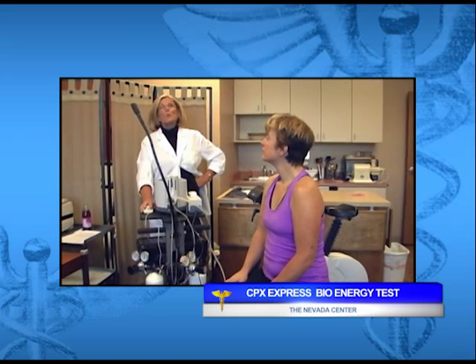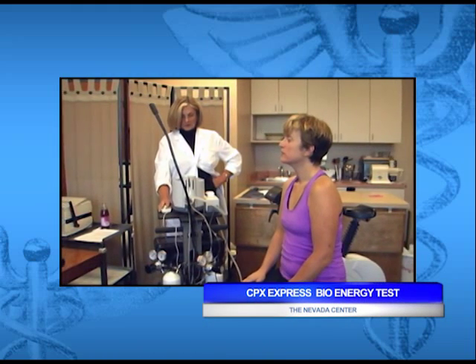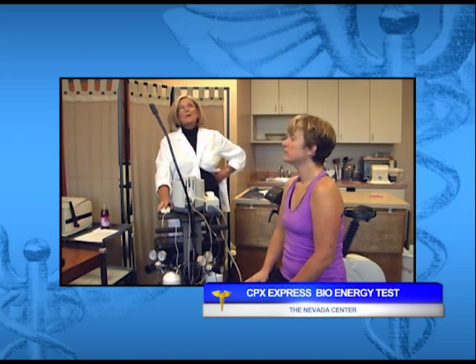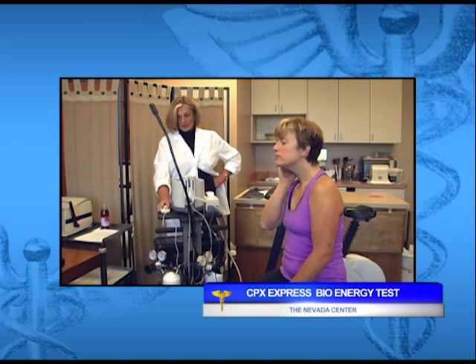It's going to ask you if you want to turn the pump off. You're going to say yes. And then it's going to ask you if you want to select a test credit or use a test credit. And you're going to say yes. If you hit no, you're going to lose all your data.